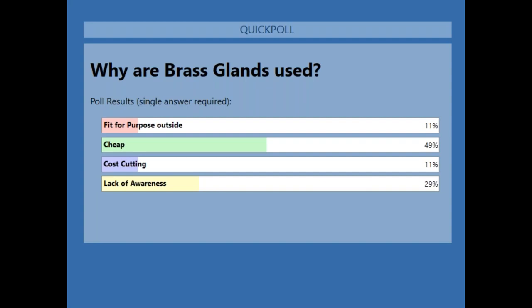Because they're cheap. It's a cost-cutting method and lack of awareness within the industry. Now, for those who said that it's fit for purpose outside, how much more evidence do you need? If it costs you an extra $1 per gland, why are you going to put your personnel and your facility at risk? A corroded device that disconnects, now the cable is no longer earthed. You are putting equipment and personnel at risk of electrocution. You've lost your earthing.